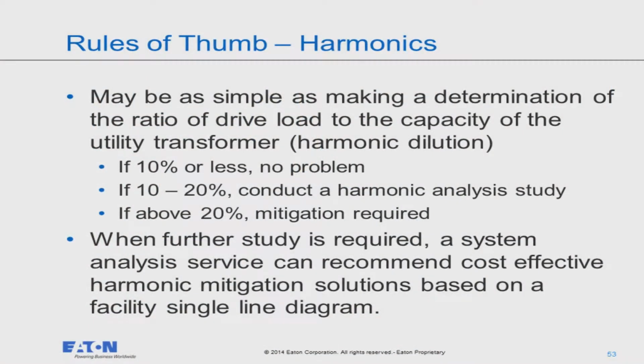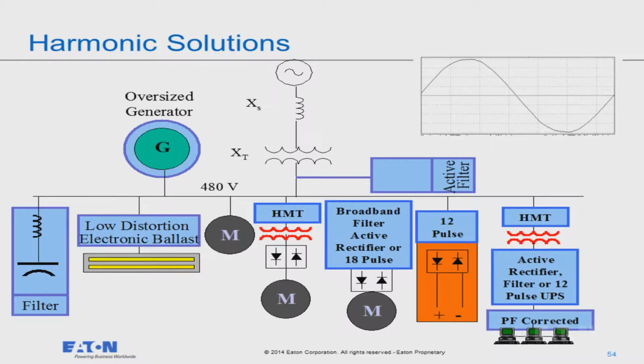That's kind of the breaking point of, okay, now we know we have some harmonics in the system. What can we do about harmonics? And what can we do to get rid of them? There's a whole lot of different solutions here, including filters, low distortion loads for lighting and things like that, harmonic mitigating transformers, broadband filters, 12 pulse rectifiers, a lot of different things, active filters, or maybe you just oversize your generator.